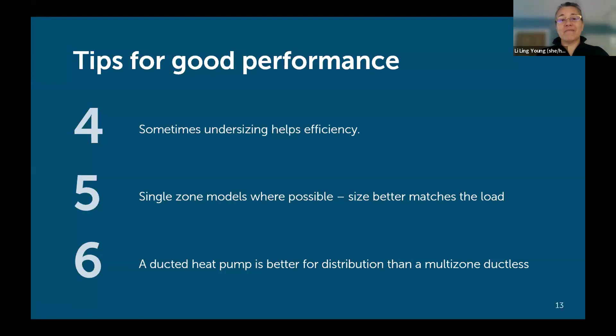And a ducted heat pump: if you do need to spread heat around to different parts of the building, a ducted heat pump is going to be better for getting heat into different rooms than a multi-zone, because a ducted heat pump, when it's heating, has a bigger load that it can heat. I don't know how to explain this, but the slope of the line is different because it's not just trying to heat one room.